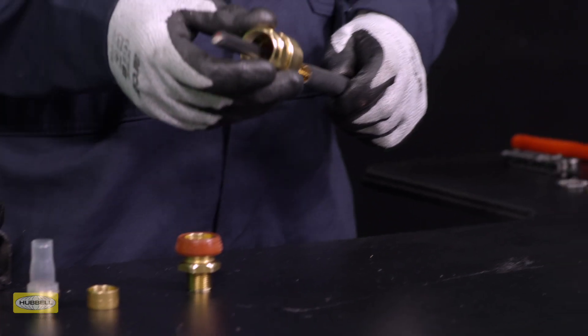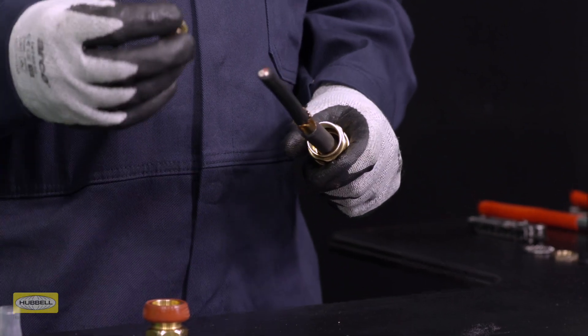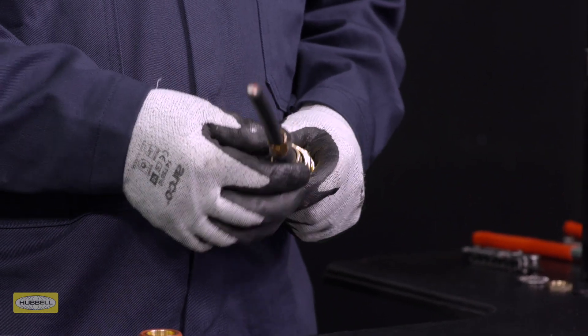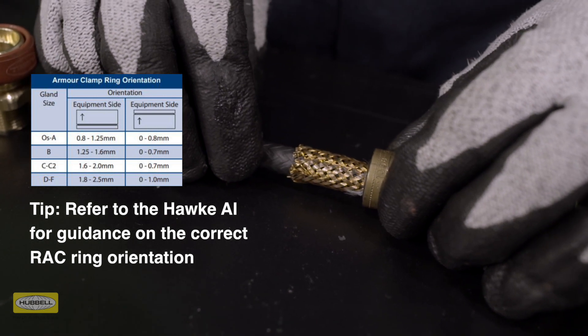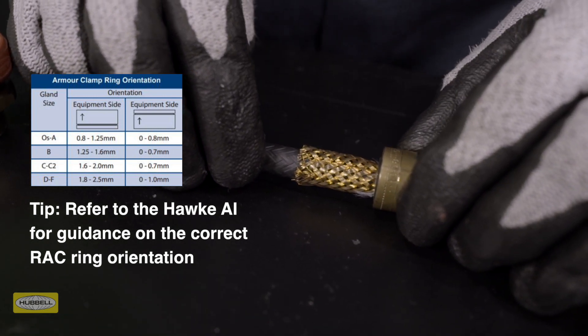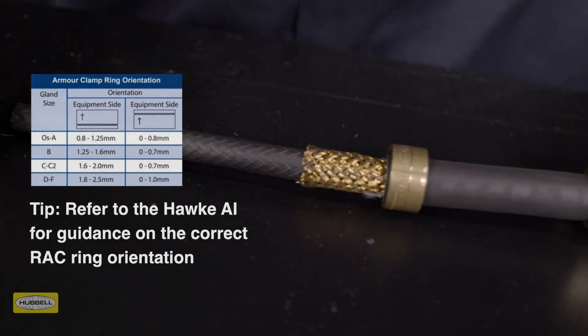Slide the back nut, middle nut, and armor clamping ring onto the cable. Ensure that the orientation of the reversible armor clamping ring is correct, with the arrowhead indicating the correct armor, braid, or tape pointing to the equipment. Always refer to the Hawke assembly instructions for guidance on the correct armor clamp ring orientation.